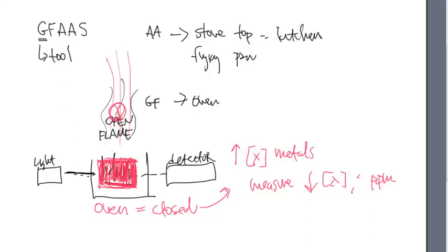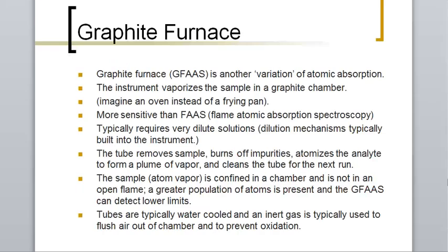...it allows me to measure lower concentrations than parts per million, and that's one of the reasons that people use a graphite furnace. They do it because in a closed system, this prevents the escape of the metals, and because of that it allows me to make measurements in the lower levels of something that I can't get to with traditional AA. So we're talking about parts per billion very easily. I do not have a problem with parts per billion levels when it concerns the graphite furnace. So it is more sensitive, it allows me to go lower in the concentration ranges, but it is a sealed chamber. And I need you to think of it like the oven part of a stove and not the frying pan part of the stove.